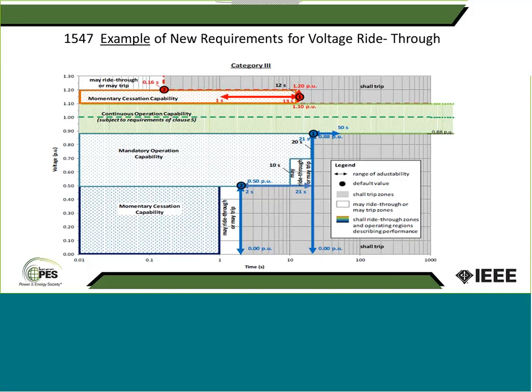Is there something about the nature of the inverter design that requires that capability there, or is it something else? No, this is more like, inverters can, if you look at this, I'm sharing the slide now, just point number 2, you can go down to basically 0. So inverters, by nature, can provide current at voltage below 50% also. It's more like the requirements that we're seeing on the distribution side, the impact on system protection, that requires this type of function. Otherwise, they can do that.